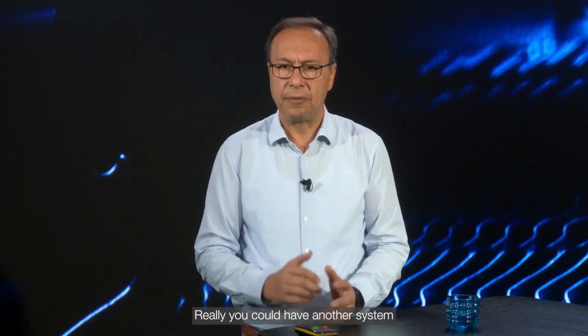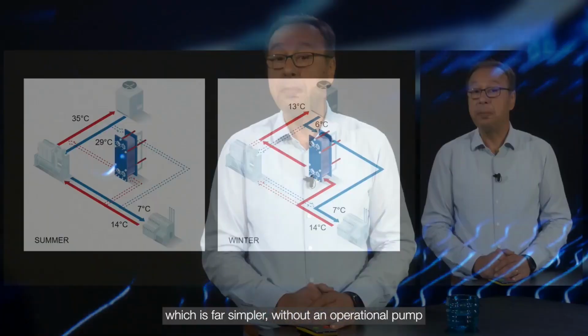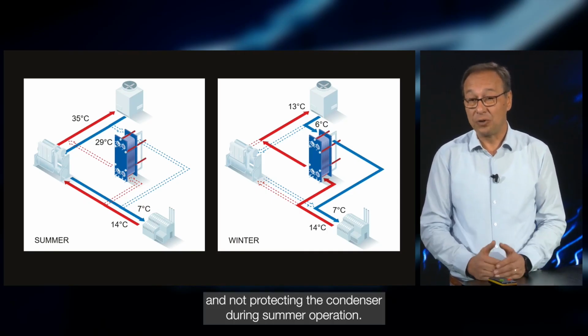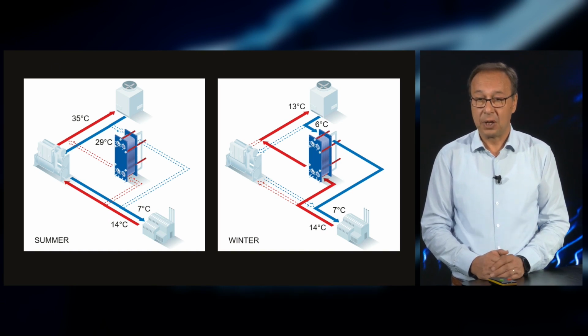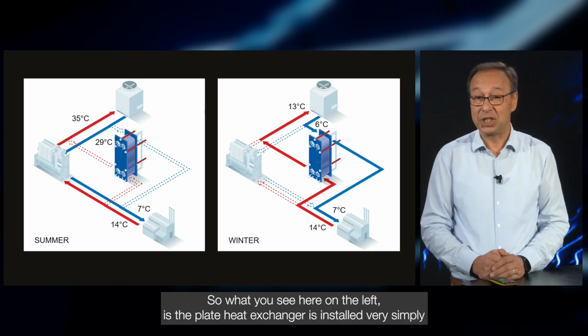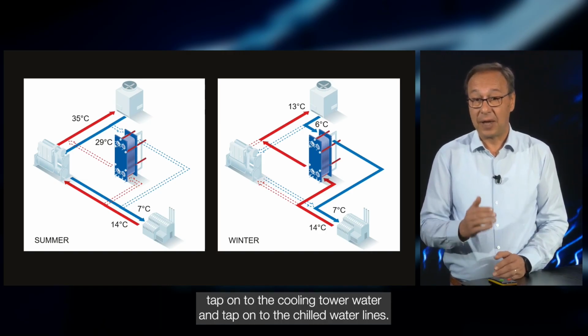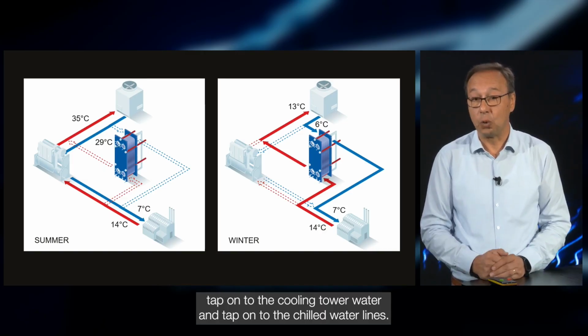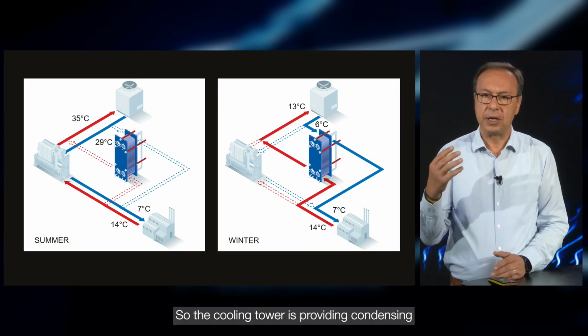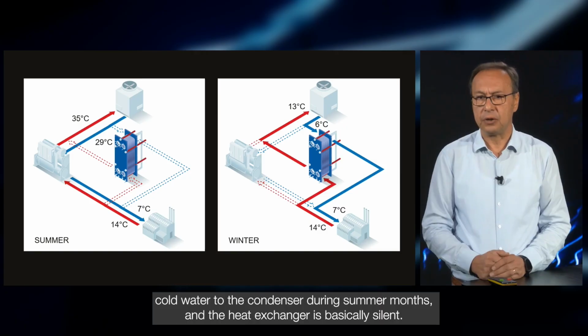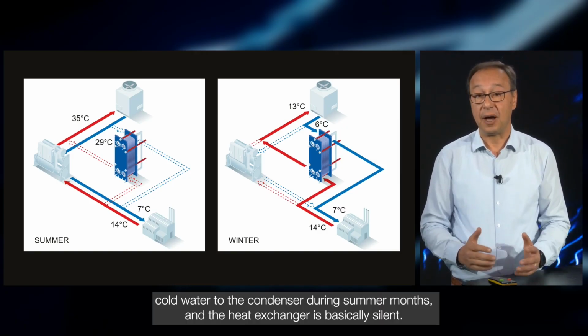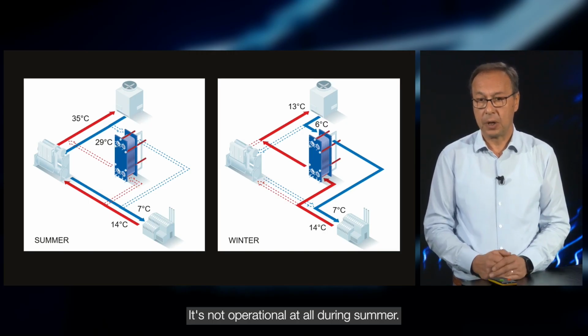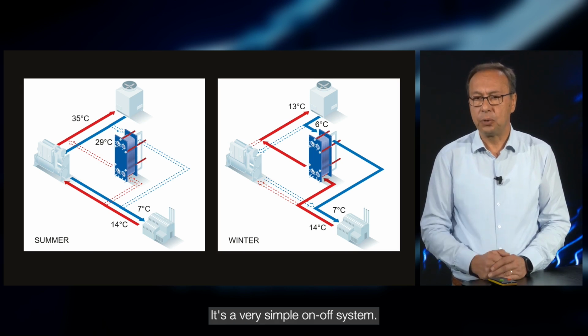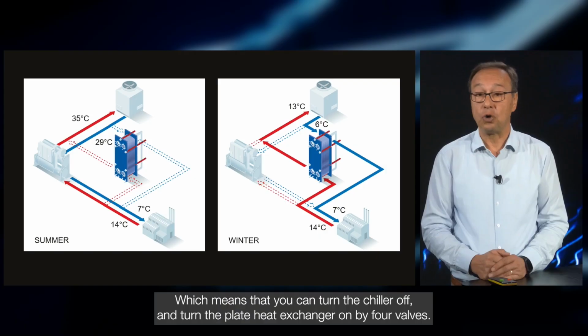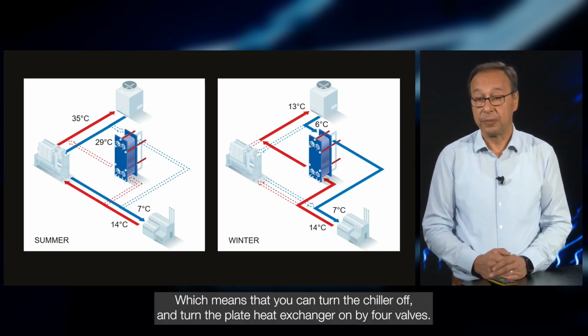You could have another system which is far simpler, without an operational pump and not protecting the condenser during summer operation. On the left, the plate heat exchanger is installed very simply, tapping on to the cooling tower water and the chilled water lines. The cooling tower provides condensing cold water to the condenser during summer months, and the heat exchanger is basically silent. When winter comes, it's a very simple on-off system: you turn the chiller off and turn the plate heat exchanger on by 4 valves. That's how simple it is.